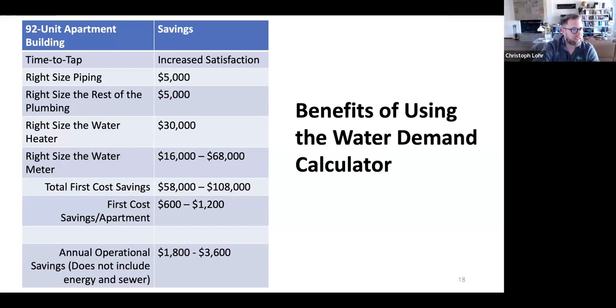But as you can see, the right sizing for the piping means thousands of dollars in savings for this 92 unit apartment complex. With less heat loss you can have a smaller water heater, and there were savings there. The water meter itself, in addition to the water heater, also had savings. Water meter impact fees are real. And so total first cost savings was in the range of, as you can see here, 60 to over 100,000. We also had first cost savings per apartment, and annual operation savings, which did not include energy and sewer. Again, a lot of water rates are tied to your water meter size. Next slide, please.